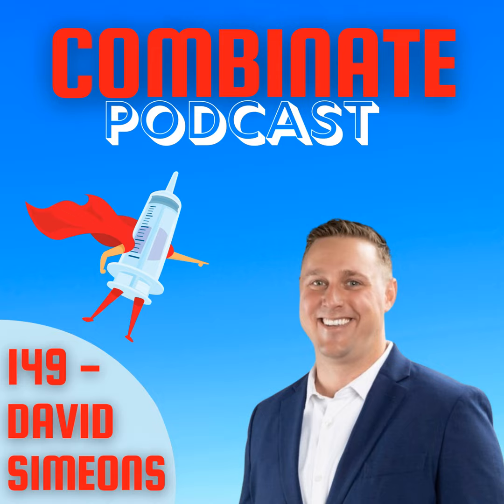Okay, makes sense. The way I had envisioned it was not like this parallel system that just goes from one side to the other. Yeah, I mean, a very easy comparison, and no, they're not the same thing, is an autoclave. An autoclave is a piece of equipment. It's a box. It has shelves that your load goes in. It has the supporting equipment to make the process work. Same thing with the freeze dryer. You have your chamber, which is your box.